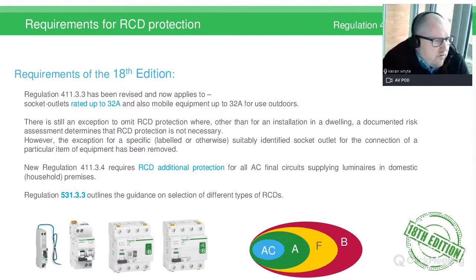411.3.3 has been revised and now applies to socket outlets right up to 32 amps and also mobile equipment up to 32 amps. So there's still an exception to RCD protection, other than for installation and dwelling, where a documented risk assessment determines RCD protection is not necessary. However, the exception for a specific labelled or otherwise suitably identified socket outlet for connection of a particular item has been removed.